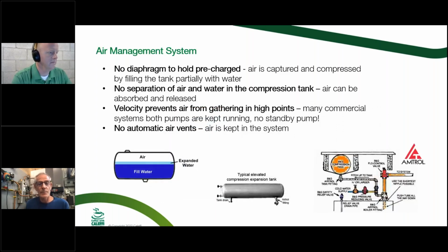So in this air management system, you can see what happens over there. What I found out in my research is that if you're going to fill a system at 12 PSI, and you fill that tank up, let's say it's a 30-gallon tank, at 12 PSI fill pressure, about 44% of that tank is going to fill up with water before you squeeze that air bubble at the top. As a result, your tank needs to be much bigger to handle that expansion.